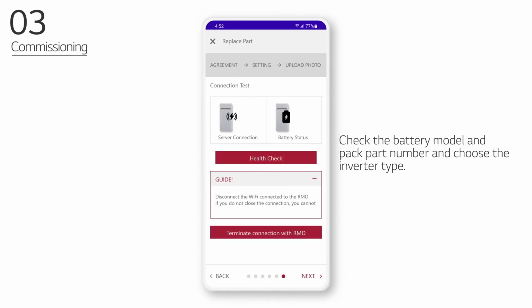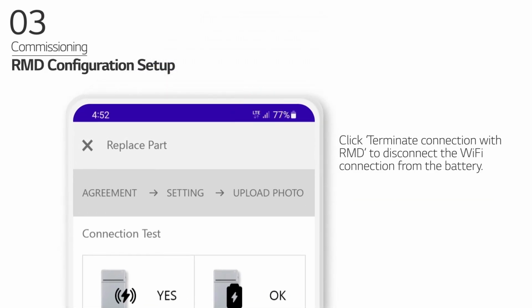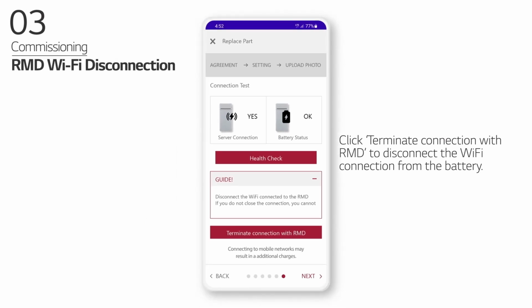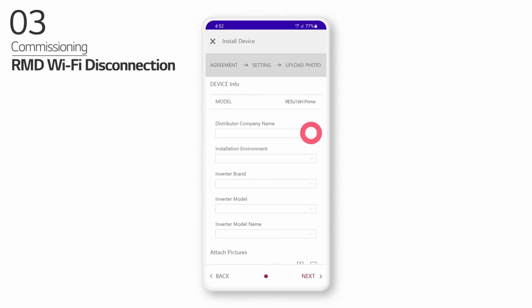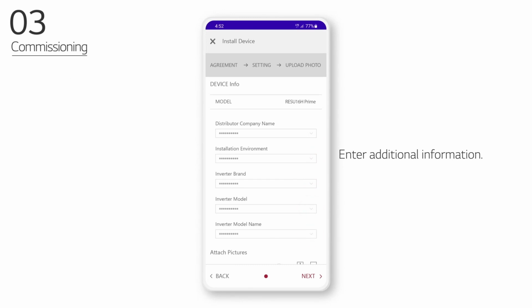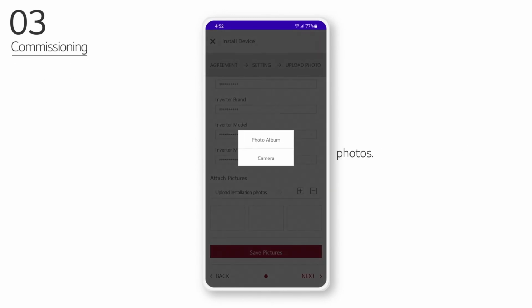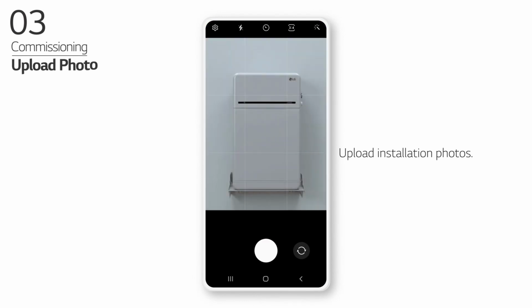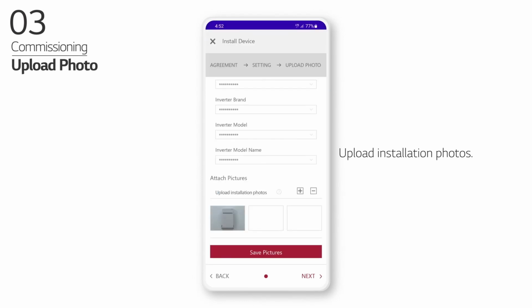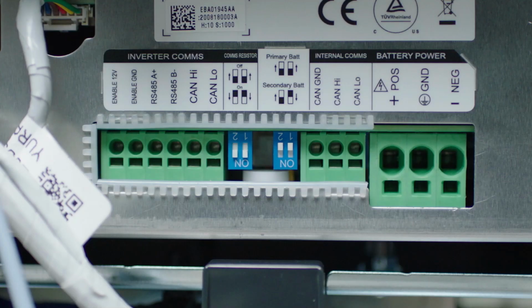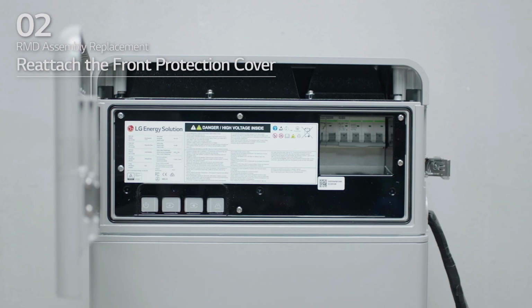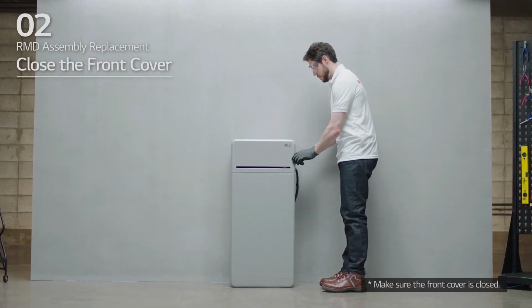Check the battery model and pack part number and choose the inverter type. Click Terminate Connection with RMD to disconnect the Wi-Fi connection from the battery. Enter additional information. Upload installation photos. Check the desired RMD settings and reattach the front protection cover. Then close the front cover.